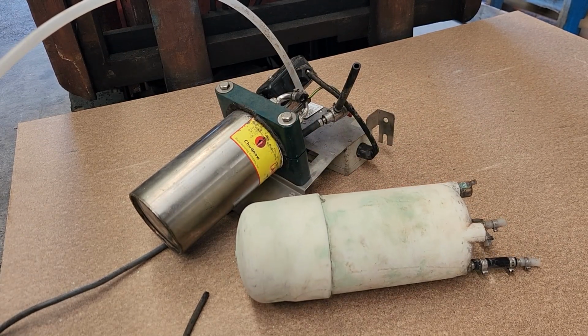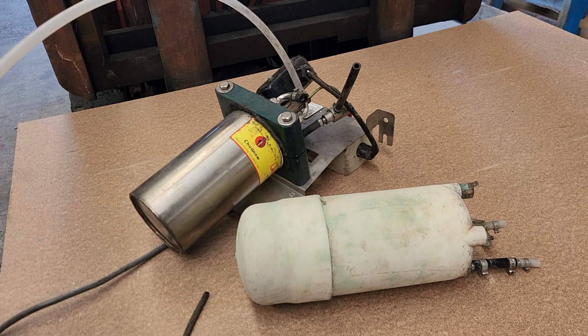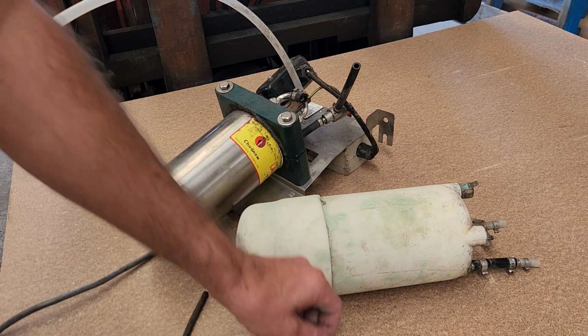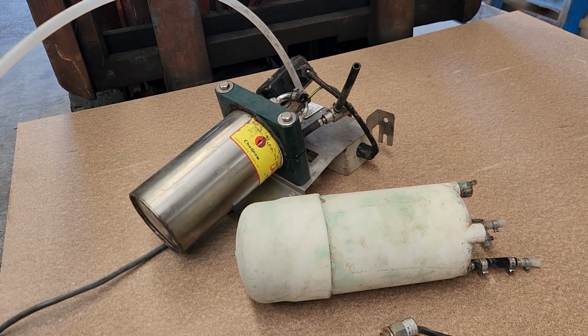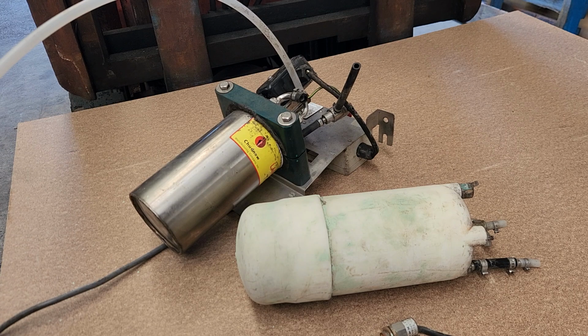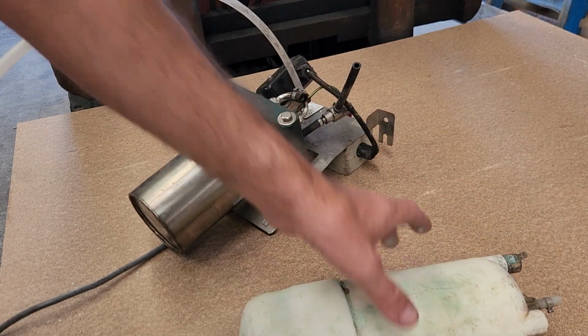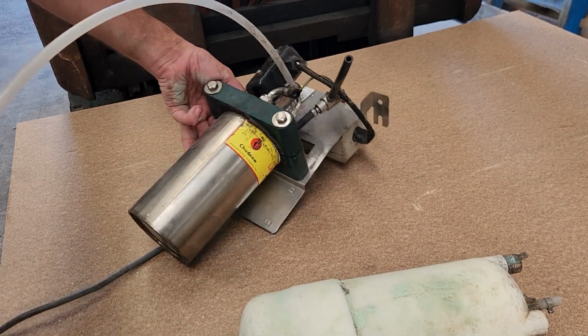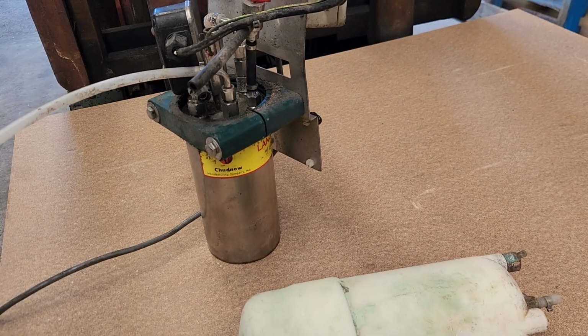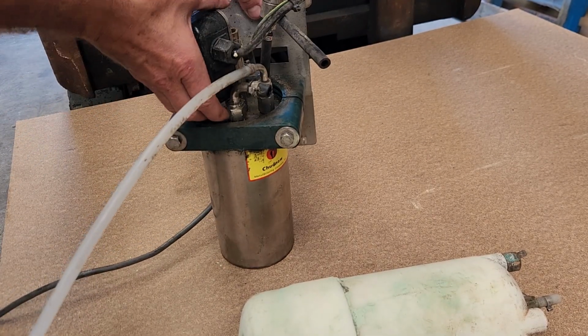So your choices are, A, your tap's turned off and your machine either doesn't have or has a broken pressure switch to test for water pressure. The one-way valve has died, the probe has died, or there's too much ice. So that's what you check for with that type of machine. Different type of machine, older types of machines have, instead of a probe, they have this.